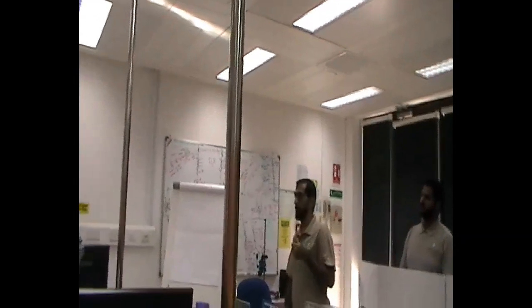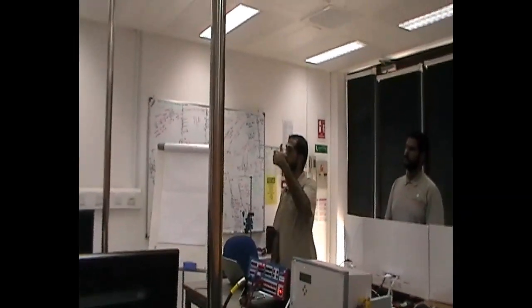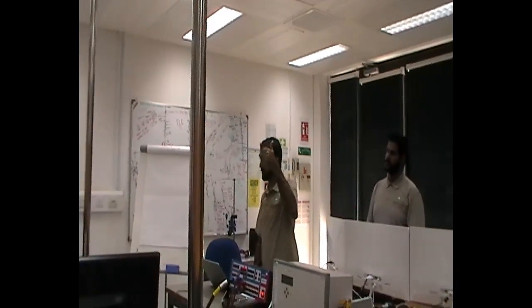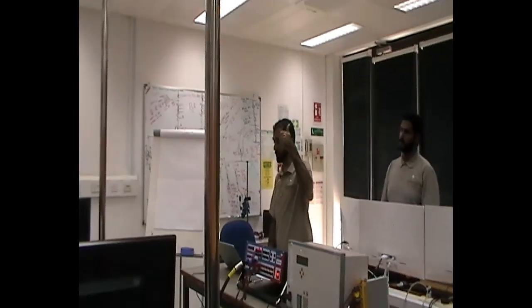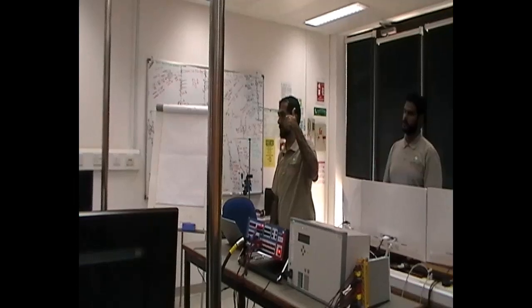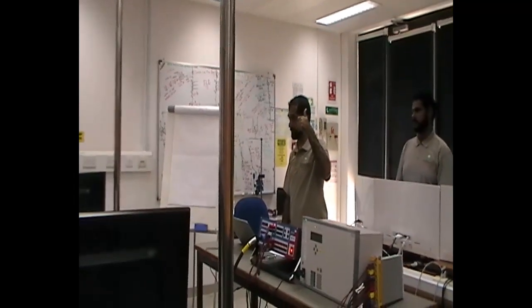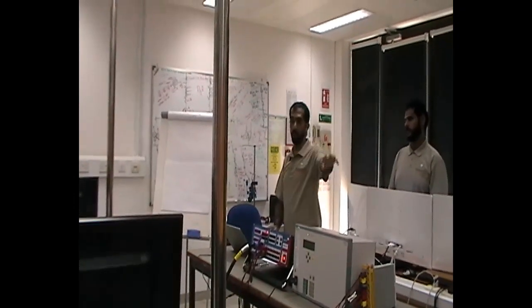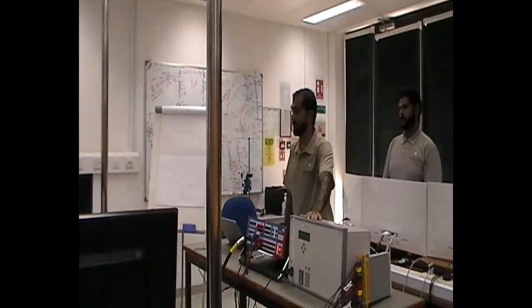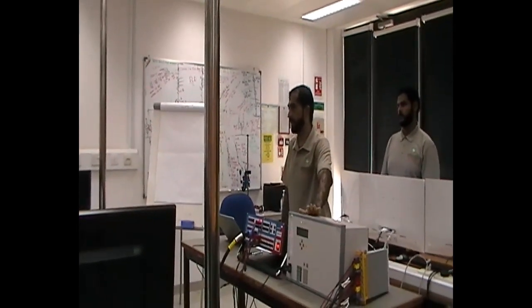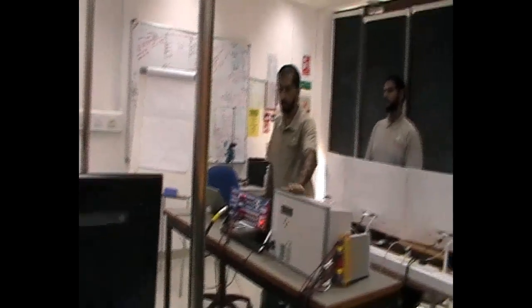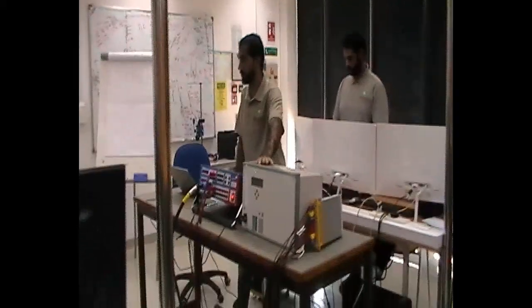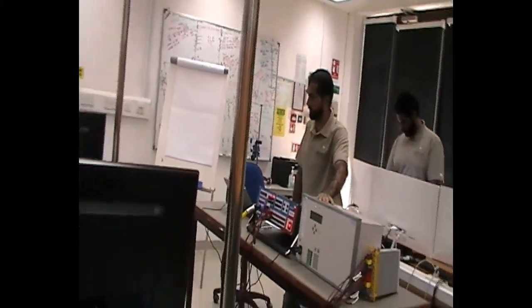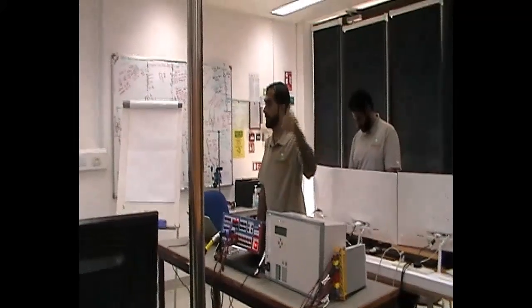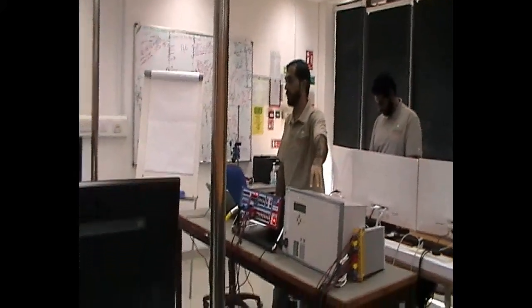So this is backup now. Zone 2 will pick up as backup, but zone 1 is main. Whenever zone 1 is enabled, it's main. No, but the relay in zone 2 is backup for the relay in zone 1. The relay is at one place, the relaying point, on the 33 kV side in the grid station, where we have 33 kV voltage. Alright? So the relay is at the relaying point, only at one point.